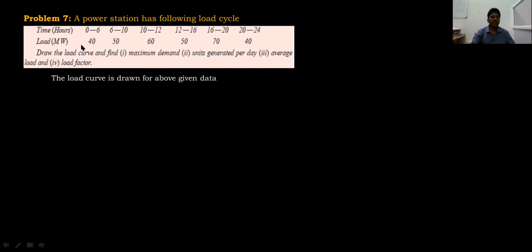If you draw the load curve, it will show you the maximum demand, and whatever data you need can be grasped from the load curve. After drawing the load curve, the first question is the maximum demand. Without drawing the load curve itself, directly by seeing the given data, we can say the maximum demand is 70 megawatts. And then, units generated in a load curve.